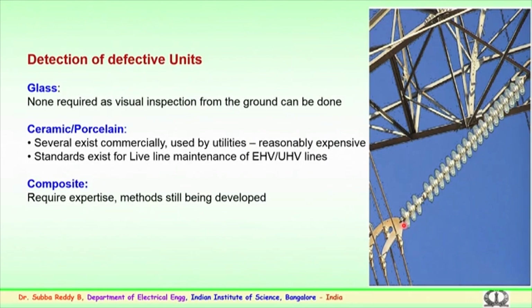Many people have tried to understand this, which will be very helpful for the utilities. Apart from physical or visual examination, there are methods to find out the defective insulators. In the case of glass insulators, as I mentioned, none are required. As you can see, if there is a shattered insulator bell, it could be visible from the ground end, and a suitable action could be taken whether to replace it immediately or depending upon the bell which is disturbed in the string.